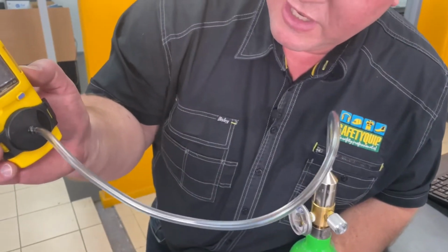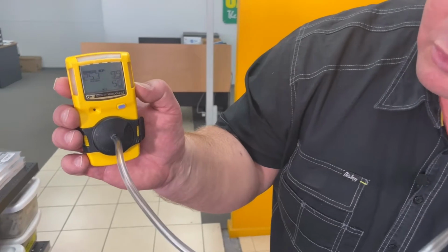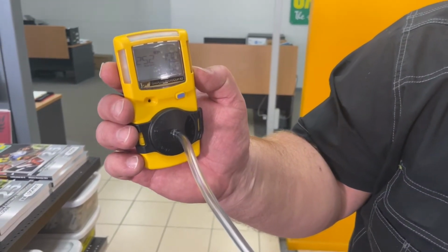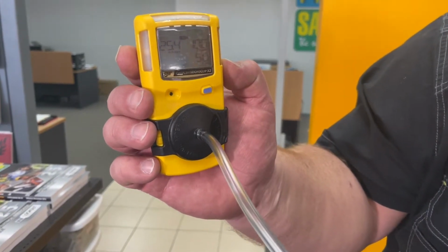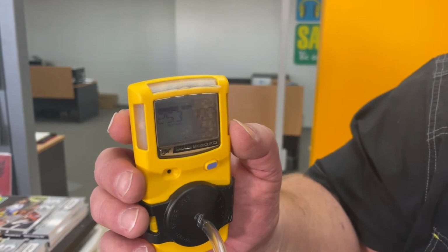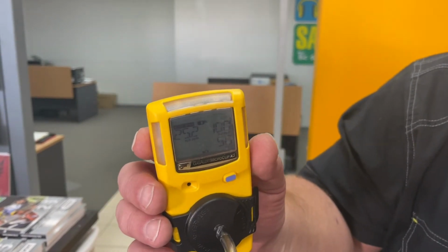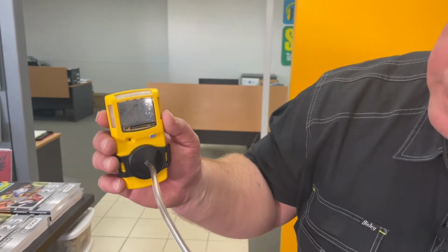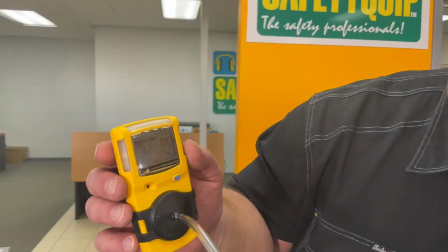So speak with our team if there's any questions on which cylinder of gas to use if you're manually calibrating a gas detector. The regulator that's on the top of the cylinder is a half a litre per minute regulator that it's dispensing the gas at. Takes a little while to do it manually. It's a bit quicker on an electronic dock, but at least this allows us to do it in the field.